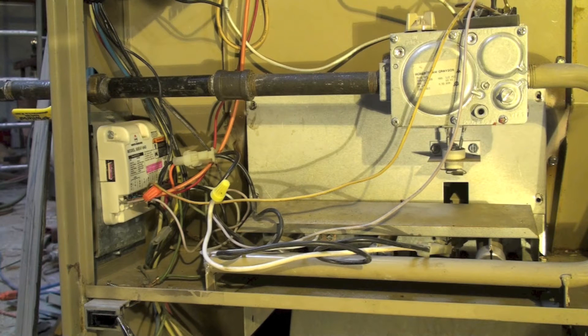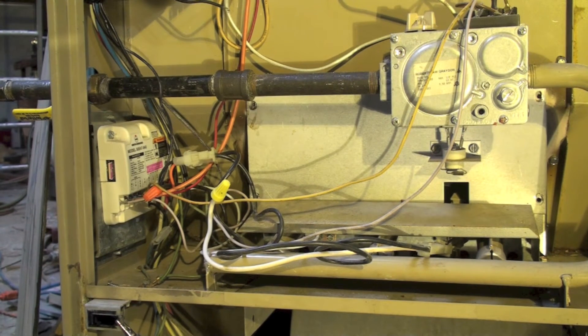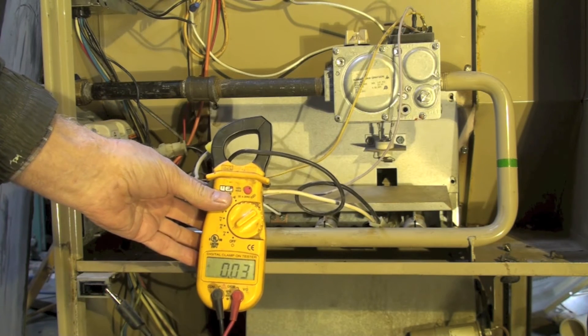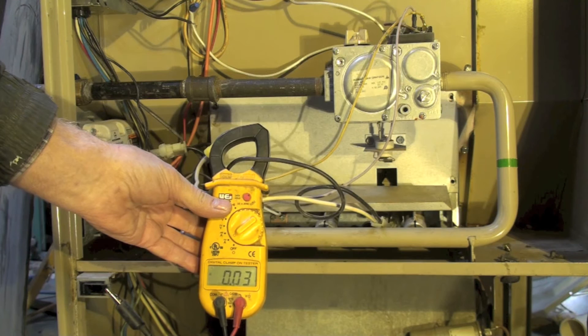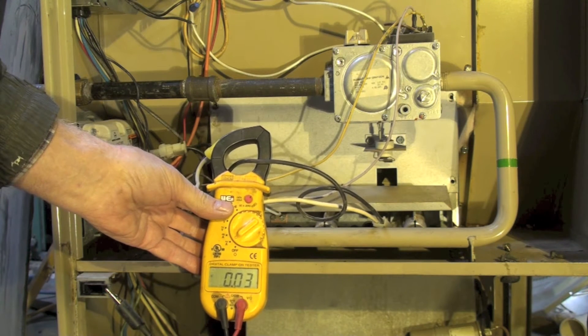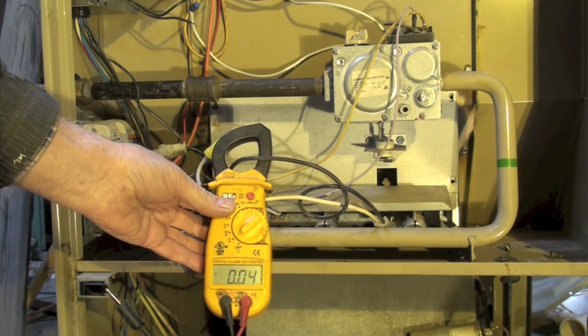Take off the blower cover, switch on the side of the furnace shut off, then turn it back on again. Now it's gonna try for ignition again. You can see I've got an ammeter on the hot surface igniter. I'm not getting any current - the hot surface igniter is not coming on because I'm not drawing any amperes. I should draw about three amps.